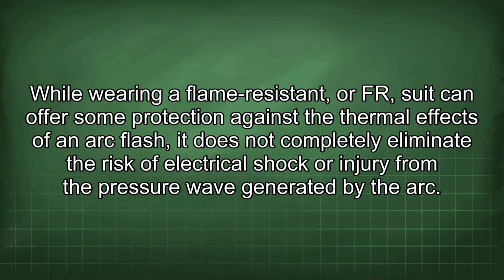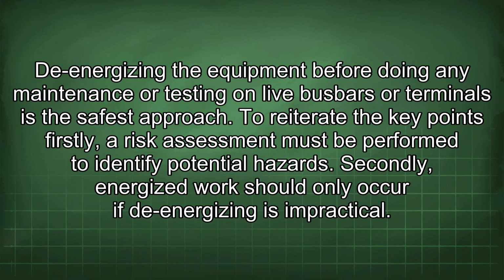While wearing a flame-resistant, or FR, suit can offer some protection against the thermal effects of an arc flash, it does not completely eliminate the risk of electrical shock or injury from the pressure wave generated by the arc. De-energizing the equipment before doing any maintenance or testing on live busbars or terminals is the safest approach.